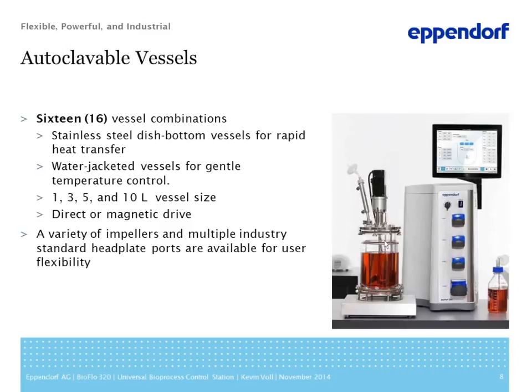Now we offer these vessels with interchangeable drive bearings, so you can use either vessel with a magnetic or direct drive. So it's not just the flexibility of the vessel connections to the controller, but also the flexibility within the vessel lines to use either autoclavable platform with any of our drive bearing housings. It's just another added layer of flexibility we've incorporated into the product.